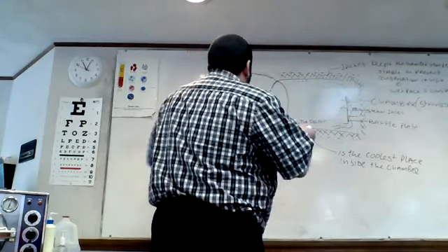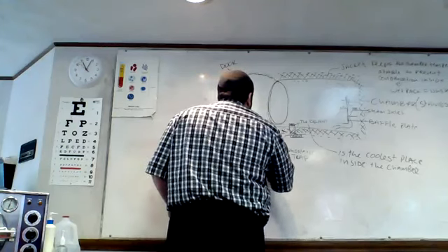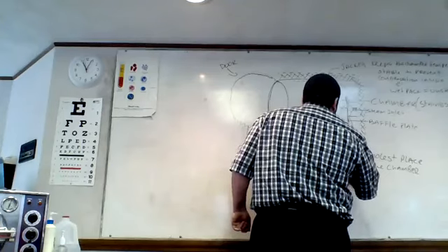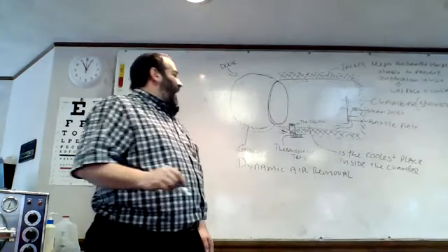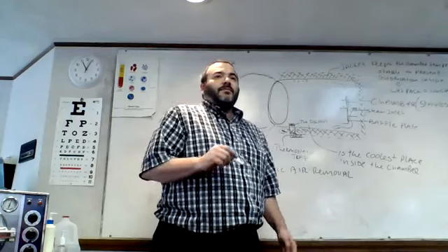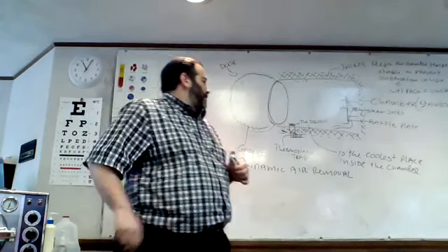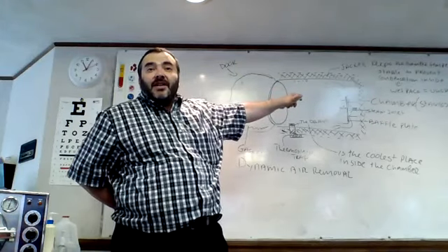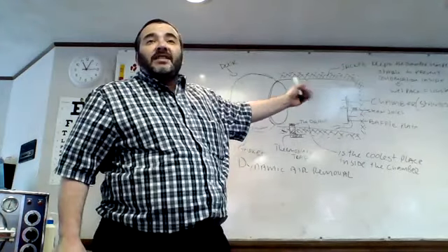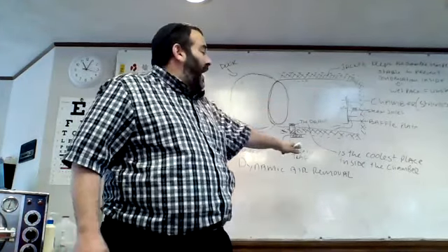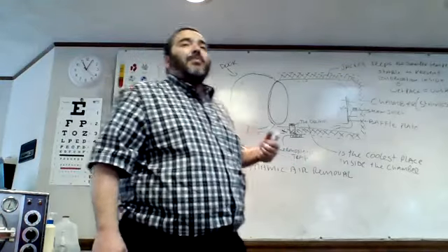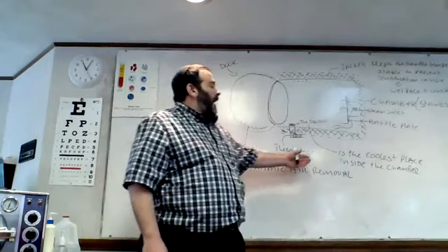Okay, so I'm going to introduce this dynamic air removal. Is this what this process is called? No, what this process was called was just regular steam sterilization, also known as gravity air displacement. I'm moving on right now to a different product called dynamic air removal. Also steam, but I'm going to explain what dynamic means. Dynamic means action, or action of air removal.